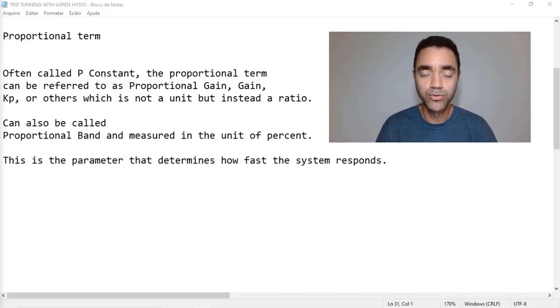It's important to mention that if you have a controller that only uses the proportional band or the proportional term, you will never reach the set point. You will always have an offset between the set point and the value, the present value. To reach the set point, you must have the integral part of the PID controller.